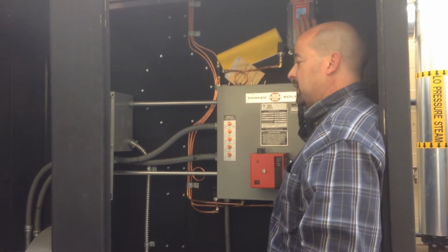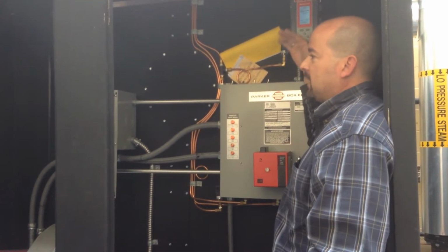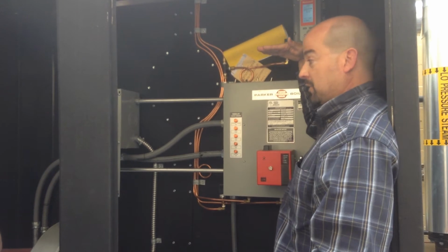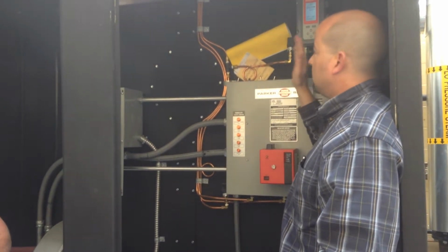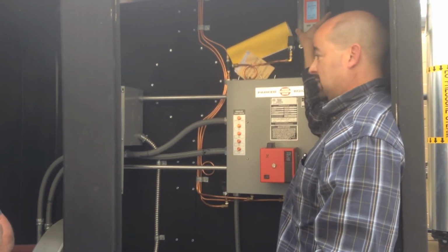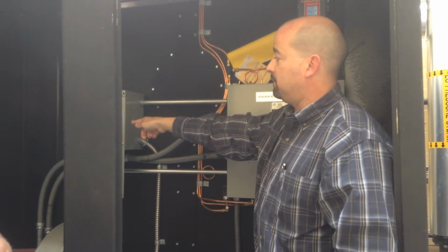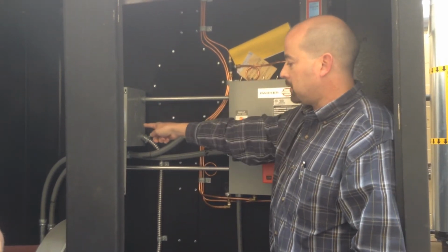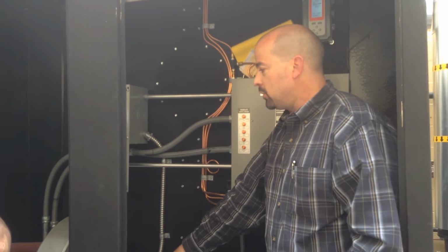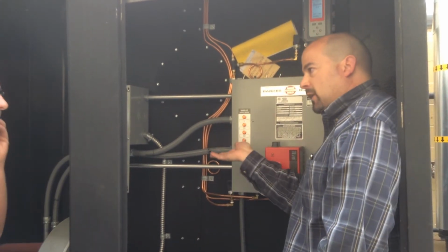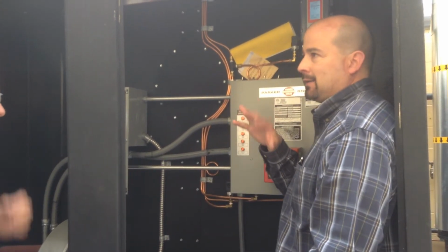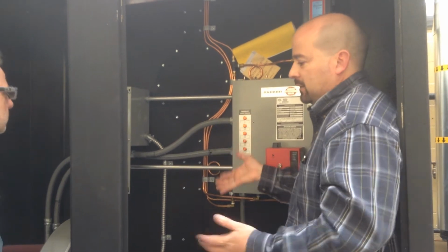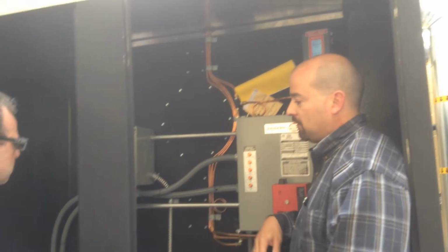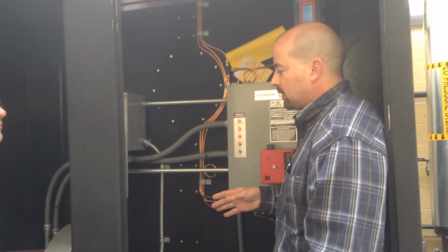But let's hypothetically say it's 5 psi. So at 5 psi, let's say the pressure's rising from 0 and it gets to 5, then it starts to modulate down. This sends a 4 to 20 signal to the variable frequency drive. The variable frequency drive sends a signal to the blower motor. So 60 hertz is high fire, and usually 20 to 30-ish, depending on the system, is low fire. So that's how that works.